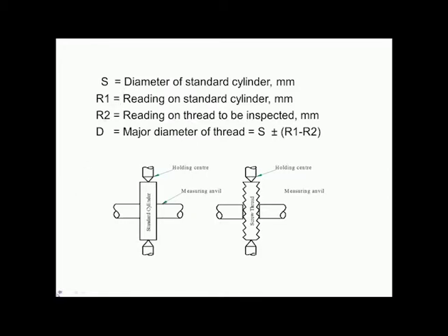S is the diameter of the standard cylinder (plain plug gauges are used). R1 is the reading on the standard cylinder and R2 is the reading on the thread to be inspected. The major diameter D is calculated using the relationship: D = S ± (R1 − R2). Whether plus or minus is used depends on whether the standard cylinder diameter is greater than or smaller than the major diameter of the thread. An outside micrometer can also be conveniently used for measurement of major diameter, taking care not to over-pressurize the thread crests.